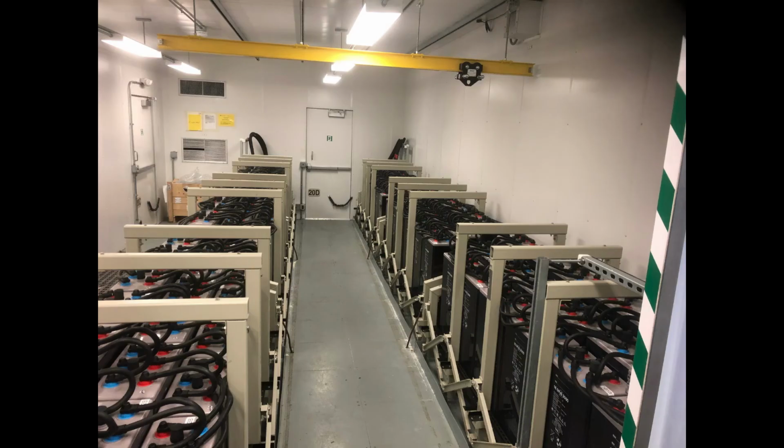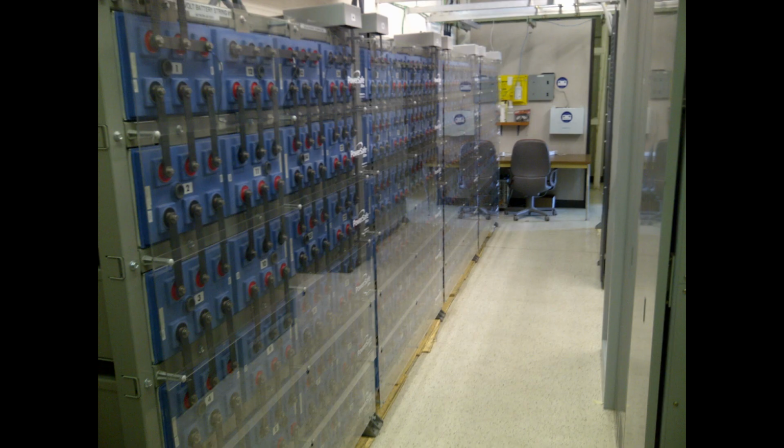With some, even after you remove the vent to let the pressure out, they still refuse to slide out easily. Because of the difficulty of this process, we developed a process that makes the removal of pretty much any size cell that is stuck in a tray a one-person, relatively easy to do process. Real simple and easy with 2 people. This process is explained in Tech Tip 20, which is pulling large 2-volt VRLA cells out of their trays with minimal effort. Well, that's a long title.